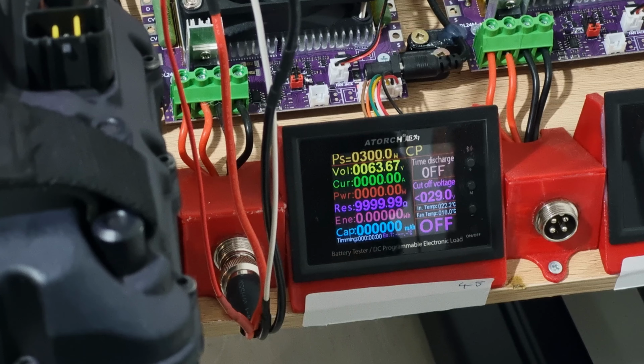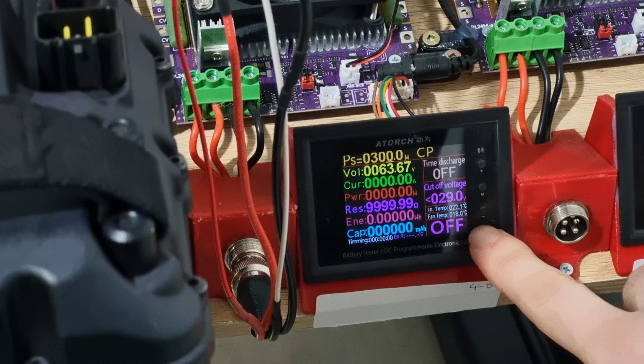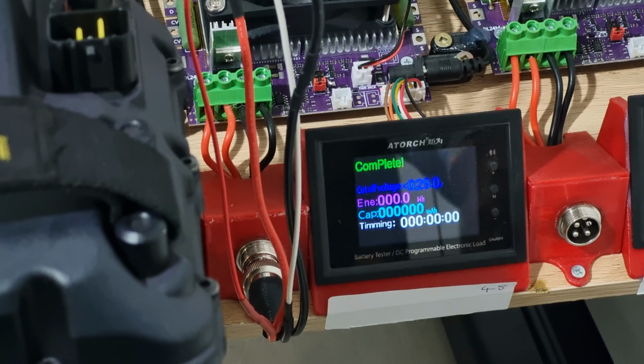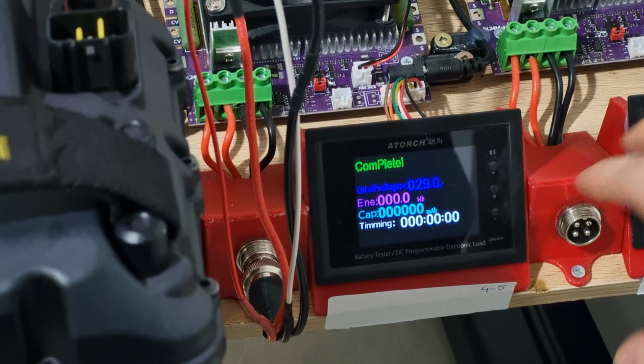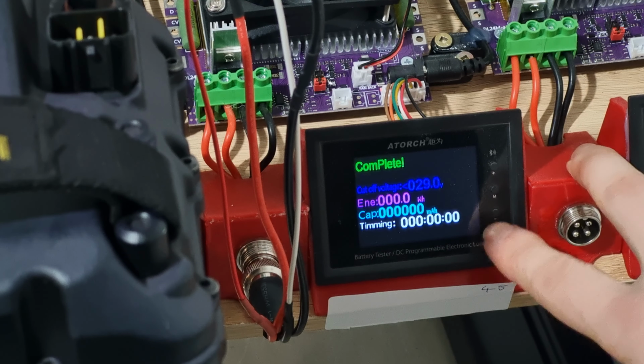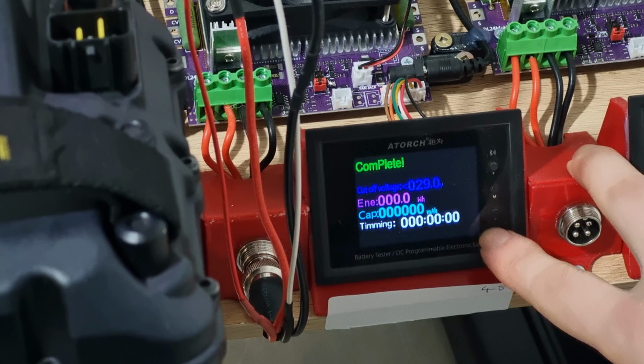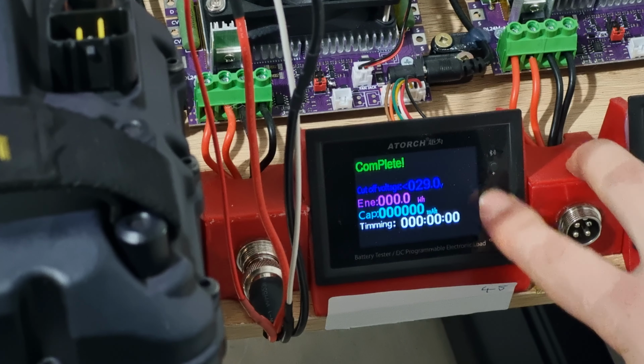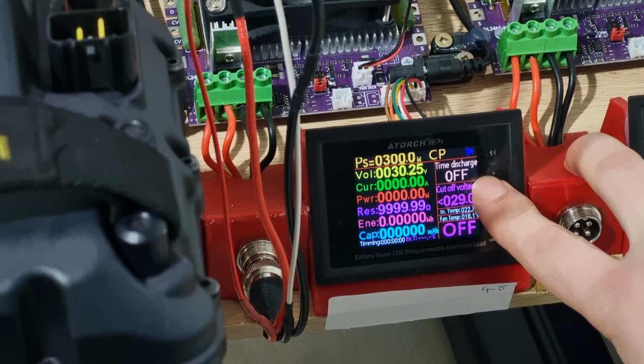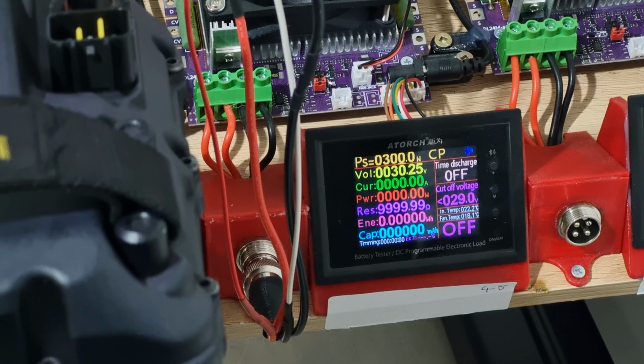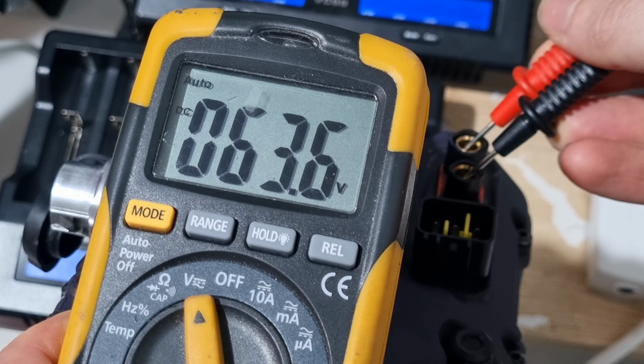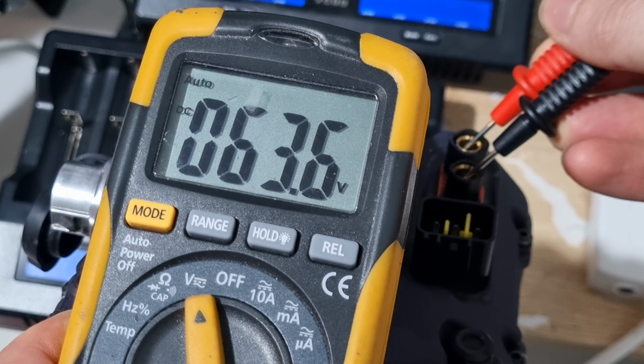Now sometimes doing this is not the full story. The BMS discharge circuit could deactivate or close as soon as there is load applied to the battery, like in this instance here, where the capacity tester immediately ended the test because the voltage dropped below the low voltage cutoff threshold, due to the programmed 300 watts that the capacity tester attempted to draw from the battery, whereas the multimeter might not be enough load in itself to trigger this cutoff.